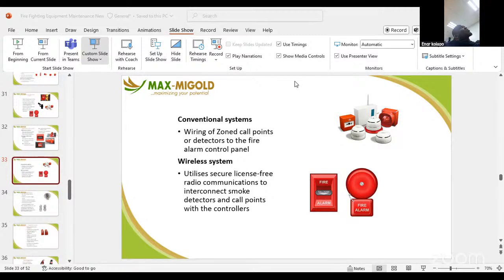We have small detectors that are actually wireless, but the danger with this is that it works on either Bluetooth or wireless connection, and is dependent on signals not being lost and batteries being healthy. If you use a wireless system, it's fast and sweet to use, but it doesn't last unless there is serious maintenance around it. So if you have a wireless system in your place, please also ask for the maintenance system, which will include the weekly checks, the scheduled replacement of the batteries, and the tests to ensure that there is communication among these. That means you activate one smoke detector and others must blink at the same time. The danger again here is that there's no panel. You don't even know where the fire is coming from. Next slide.